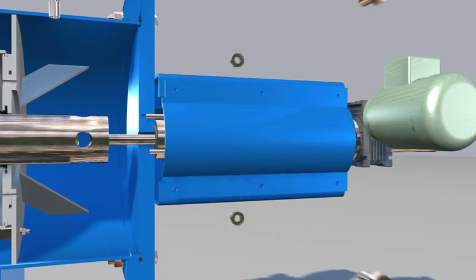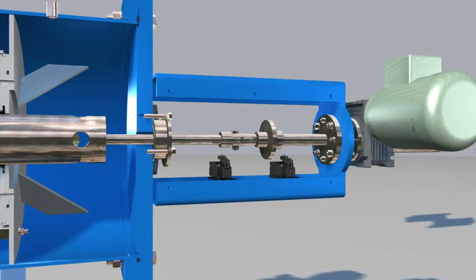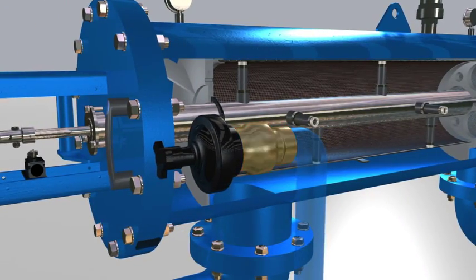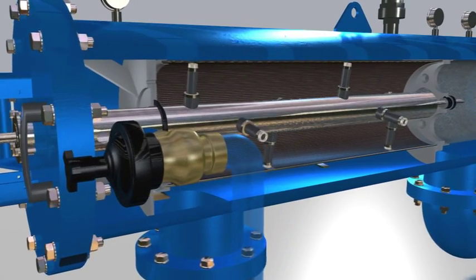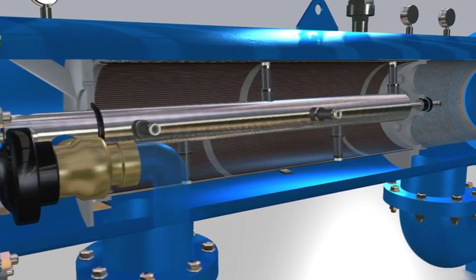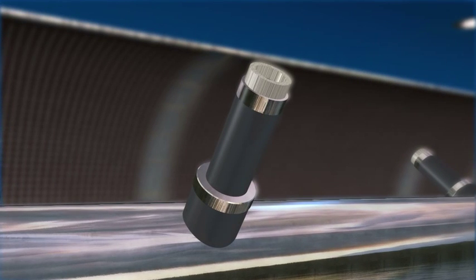The DP acts on the control panel that commands the opening of the drain valve, which is housed in the cleaning chamber, and the helical motion of the suction scanner, where the suction nozzles with nylon bristles, patented by STF Filtros, are housed.